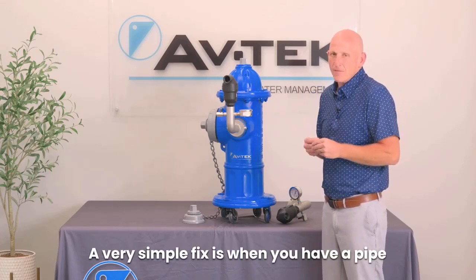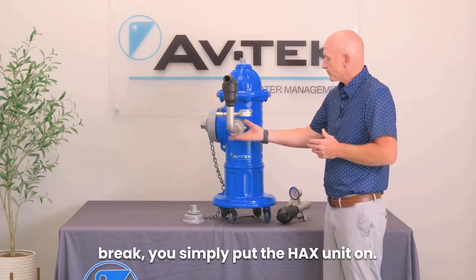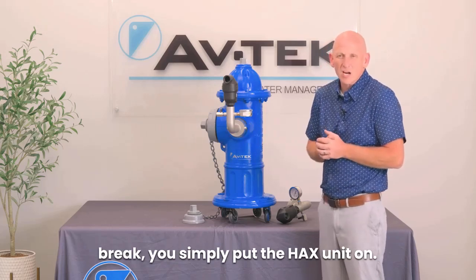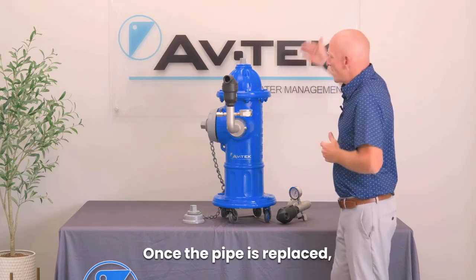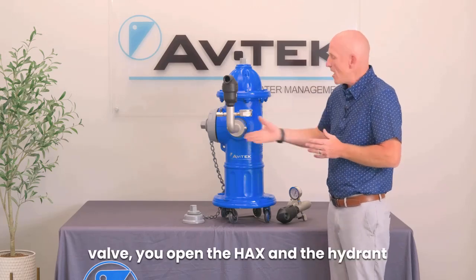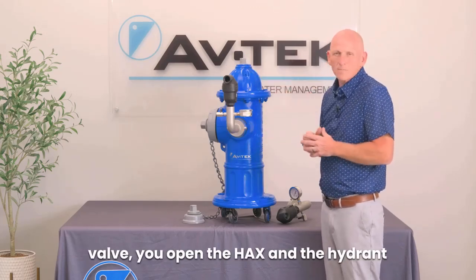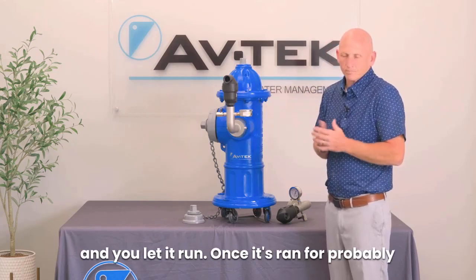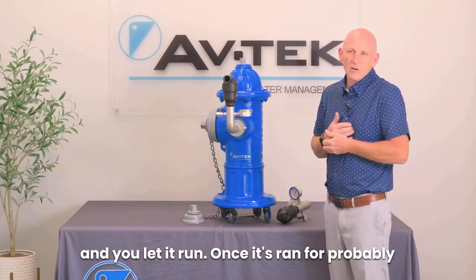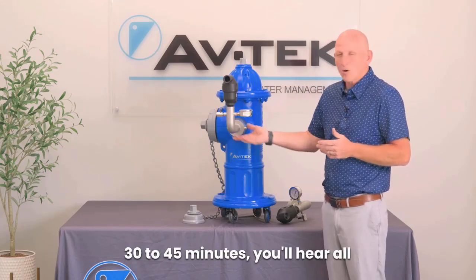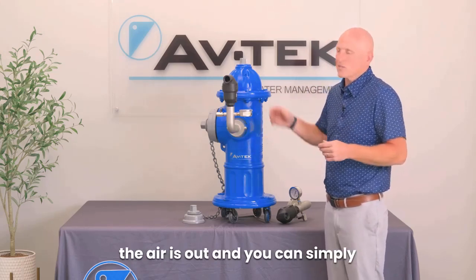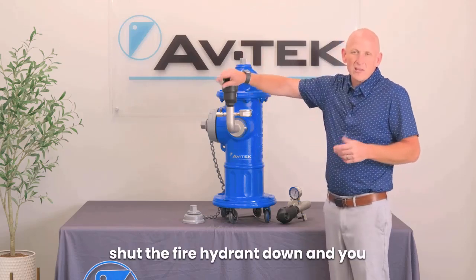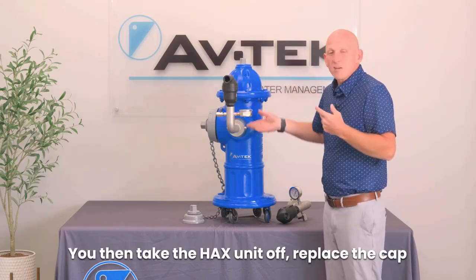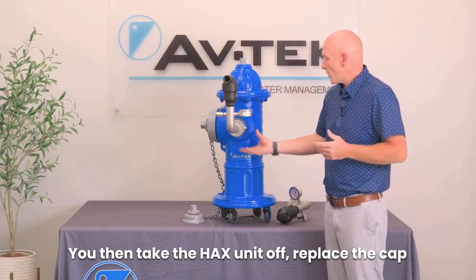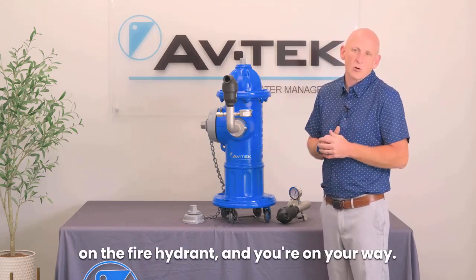A very simple fix is when you have a pipe break, you simply put the HAX unit on. Once the pipe is replaced, you open up the inlet isolation valve, you open the HAX and the hydrant, and you let it run. Once it's run for probably 30 to 45 minutes, you'll hear all the air is out, and you can simply shut the fire hydrant down, and you have all of the air out of the pipe system. You then take the HAX unit off, replace the cap on the fire hydrant, and you're on your way.